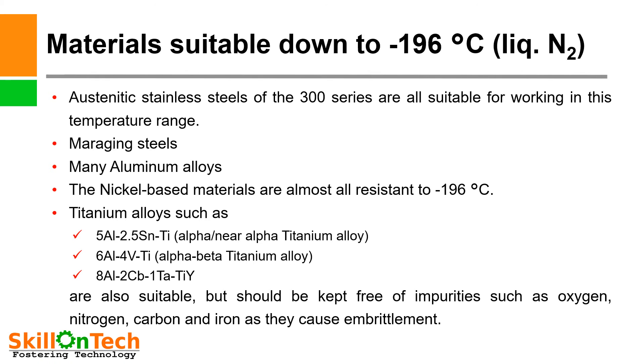Many aluminium alloys and nickel-based materials are almost all resistant down to –196°C. Titanium alloys such as 5Al-2.5Sn (alpha titanium alloy), 6Al-4V-Ti (alpha-beta titanium alloy), and 8Al-2Cb-1Ta titanium alloys are also suitable, but should be kept free of impurities such as oxygen, nitrogen, carbon, and iron, as they cause embrittlement.